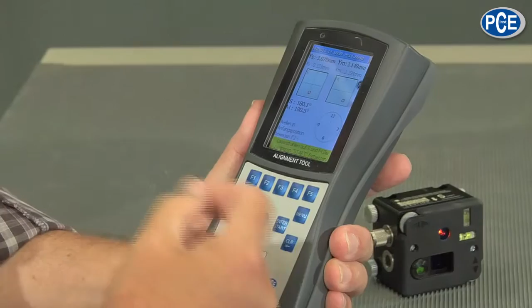As I said, the complexity and everything we can do with it is unbelievably large, even though operating it is very easy. You look at it, align things roughly, and then start to measure. Whichever part is movable - the machine or generator - the other must stay fixed; they can't both move. Naturally you can save all this data onto a memory card or onto a computer, a connection cable is included, and it's also powered with a power pack so you're independent of a socket. A measuring device of the absolute top class - I think I'll be working with it for a few days because it's not only good but interesting.